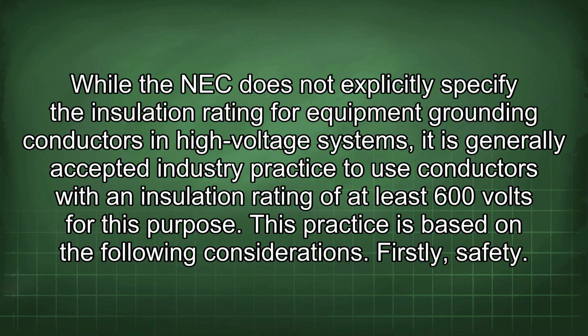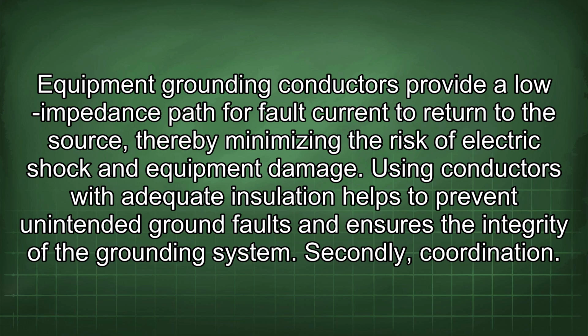While the NEC does not explicitly specify the insulation rating for equipment grounding conductors in high voltage systems, it is generally accepted industry practice to use conductors with an insulation rating of at least 600 volts for this purpose. This practice is based on the following considerations. Firstly, safety. Equipment grounding conductors provide a low impedance path for fault current to return to the source, thereby minimizing the risk of electric shock and equipment damage. Using conductors with adequate insulation helps to prevent unintended ground faults and ensures the integrity of the grounding system.